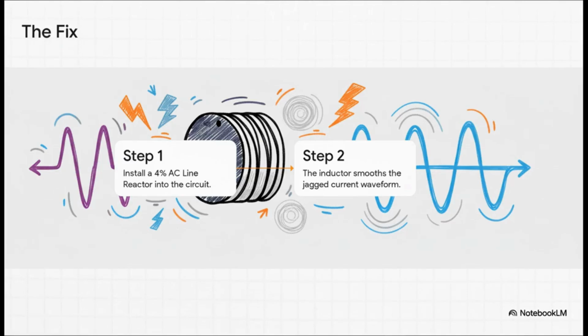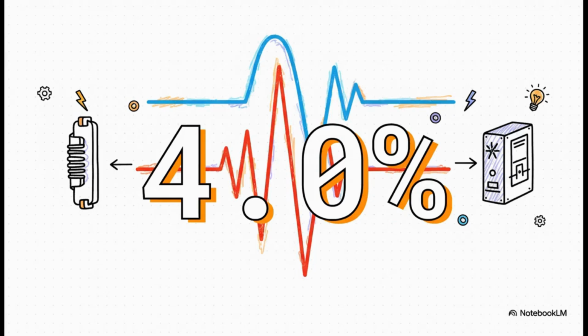So what's the fix? Well, let's start with the simplest solution. We're going to install a 4% AC line reactor. This one simple component immediately gets to work smoothing out that jagged current draw from the drive. And look at that result. The total harmonic distortion plummets all the way down to 4.0%. Just like that, with one simple and relatively cheap component, the system is now compliant, it's more efficient, and it's under way less stress. That is a huge win.